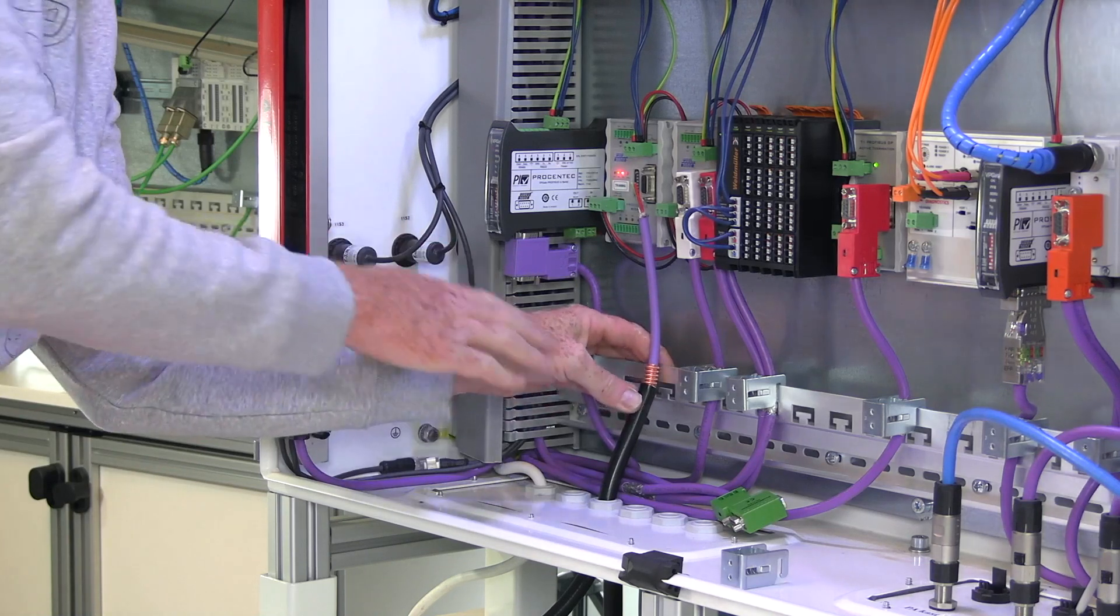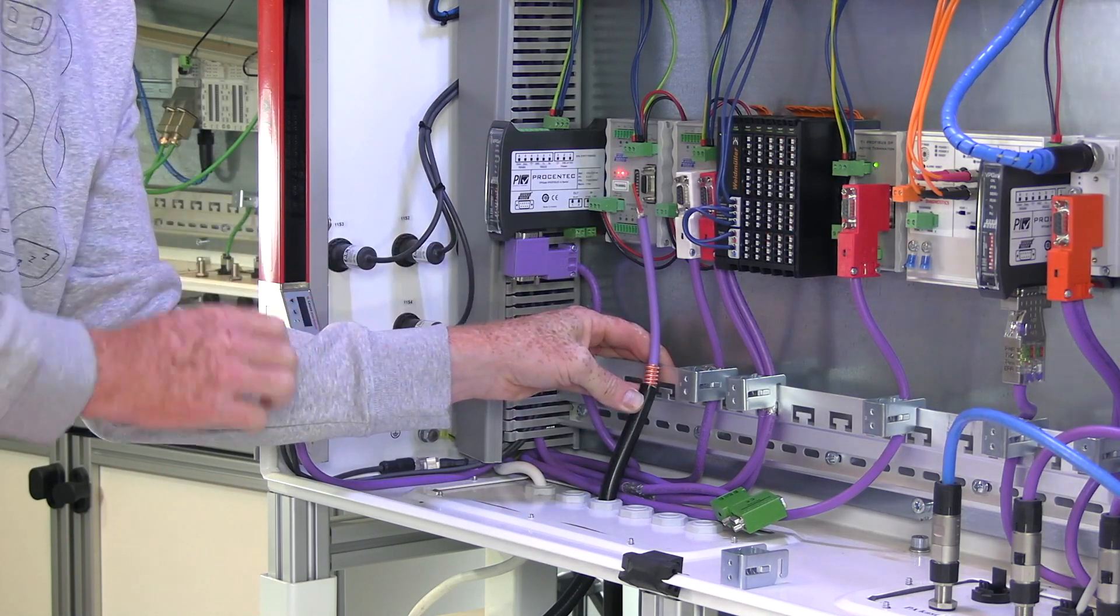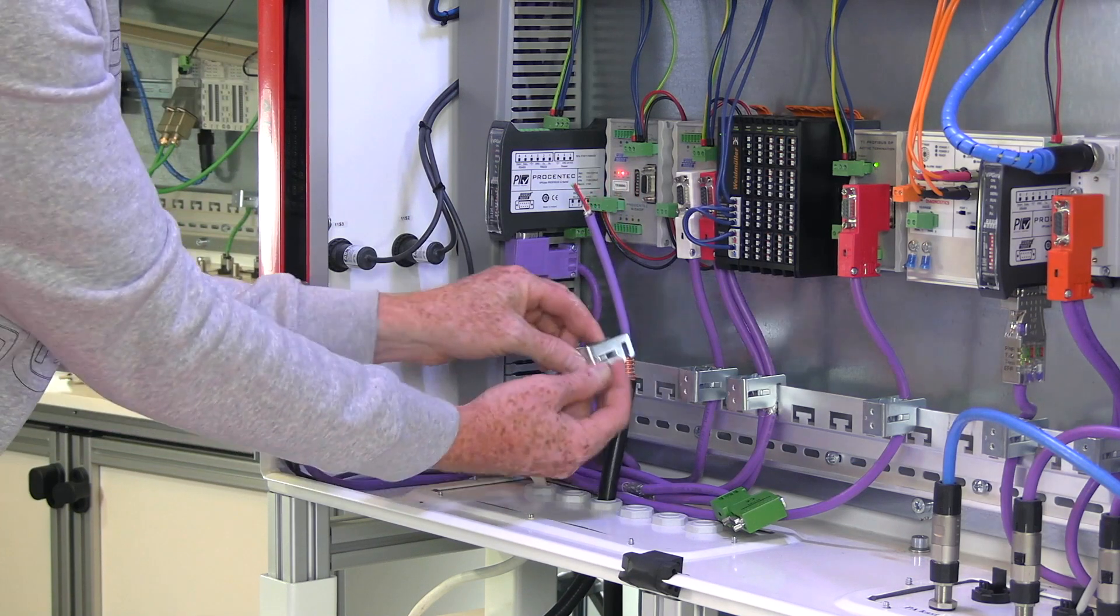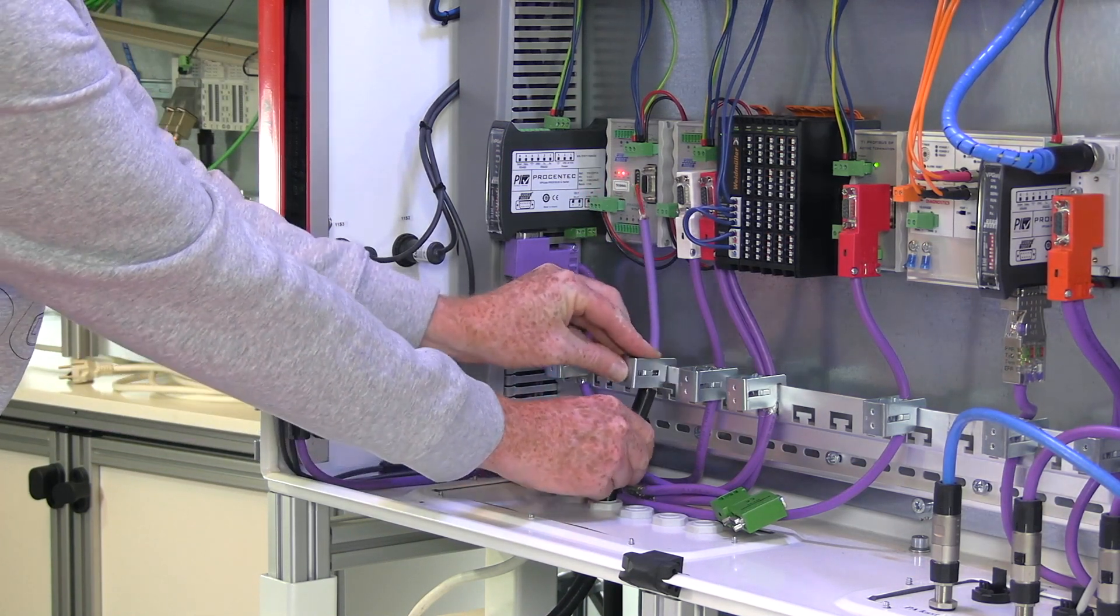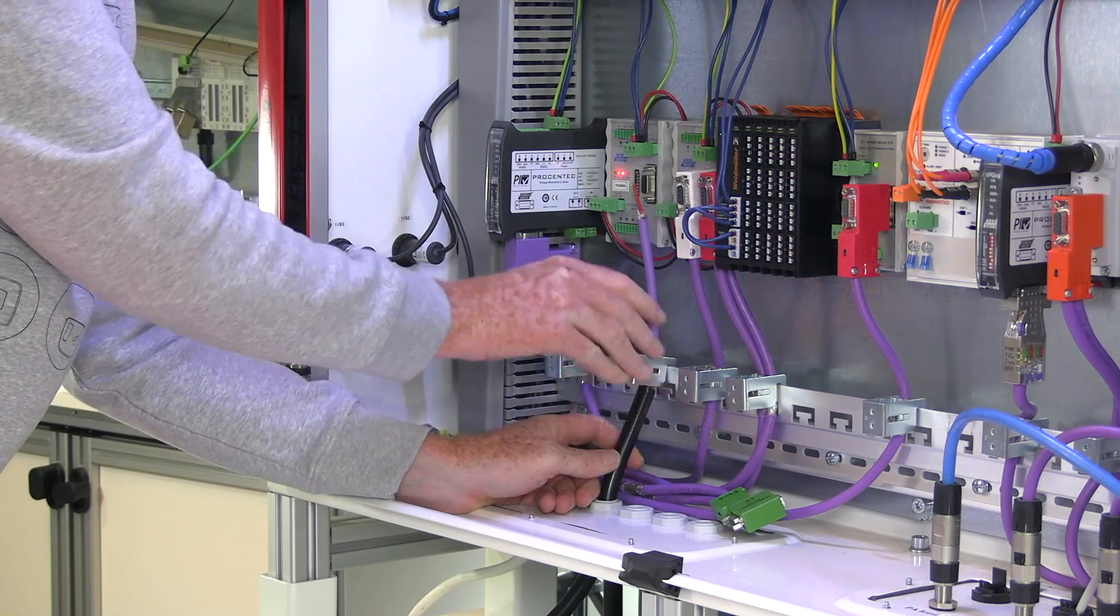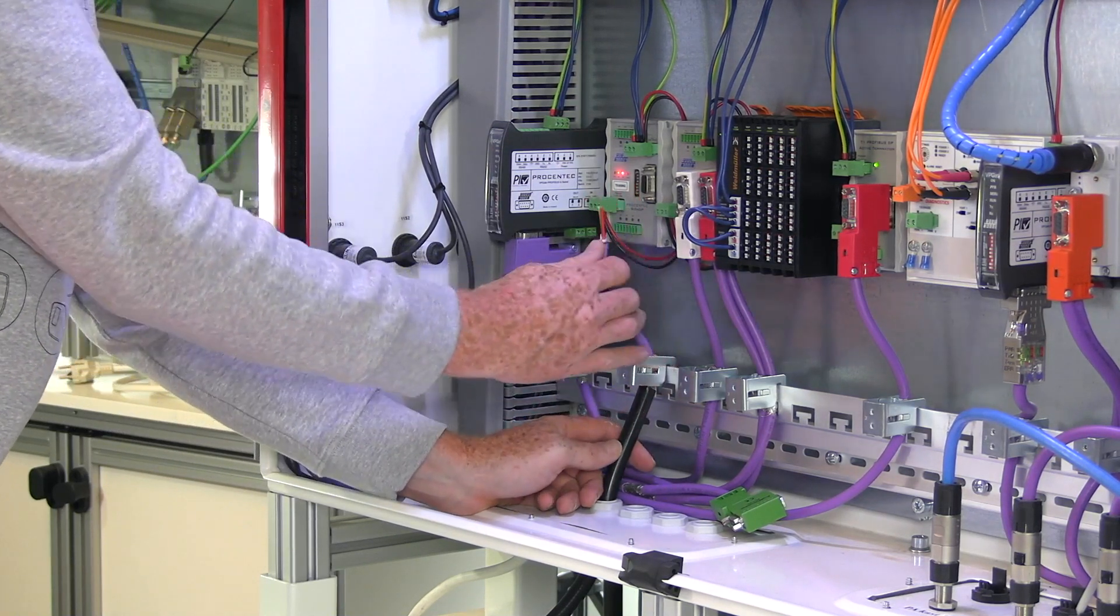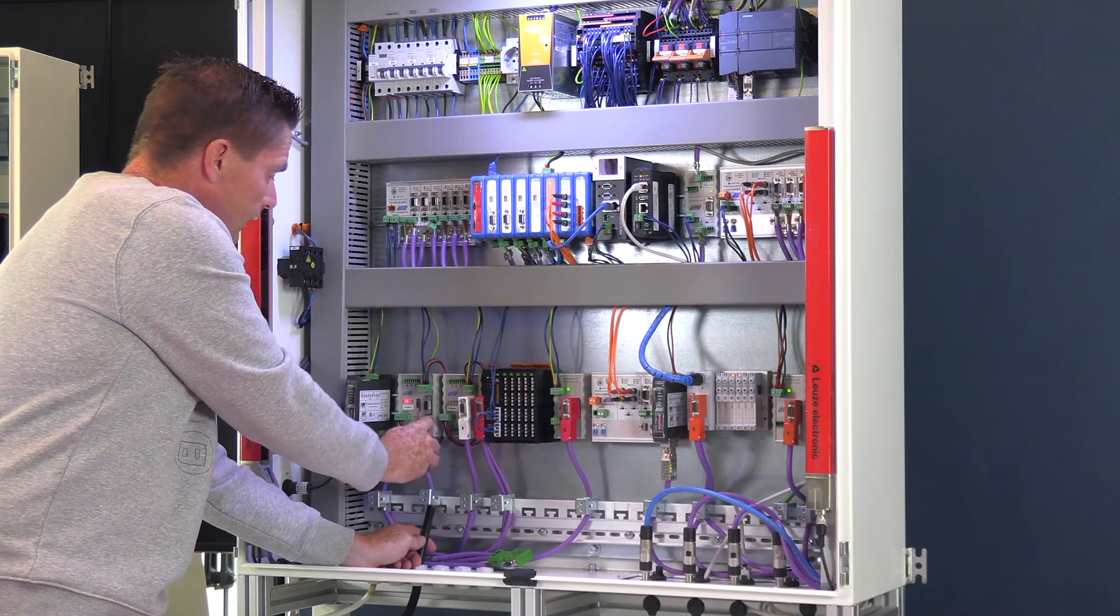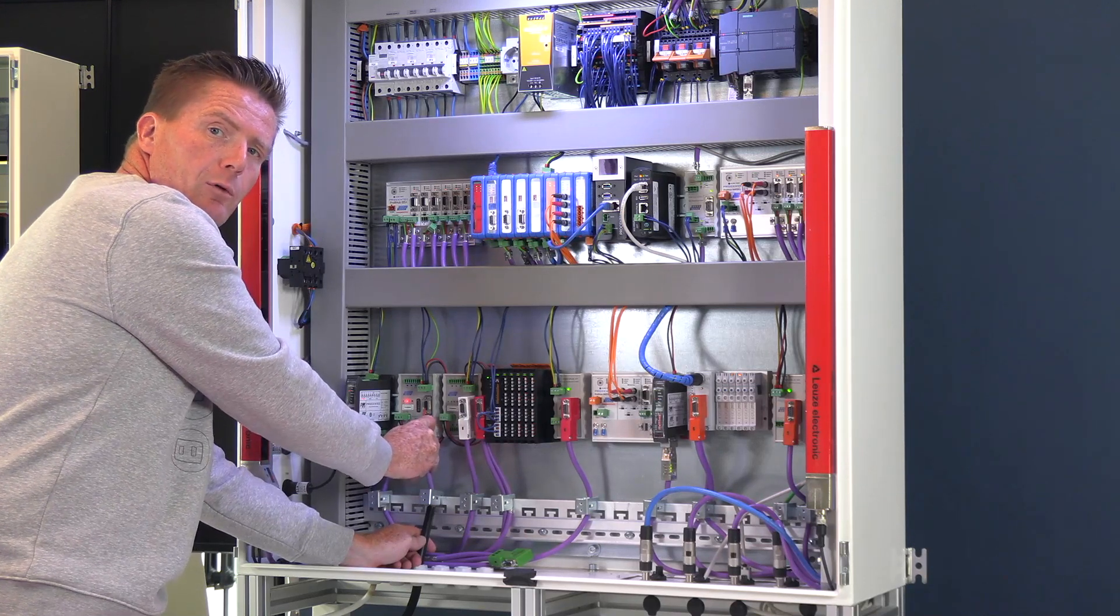So I'll place the copper against the ground rail, use my ground clip, place it over it. And now my EMC cable is connected to the ground rail. And I can connect my Profibus cable like we always do, with my extra shield of my Profibus cable for extra protection.